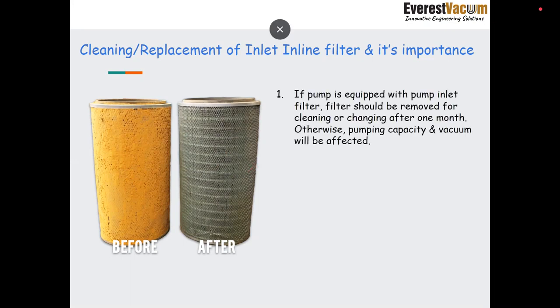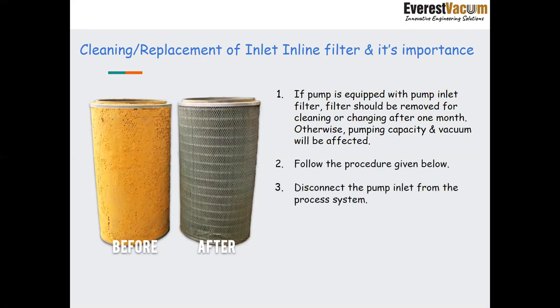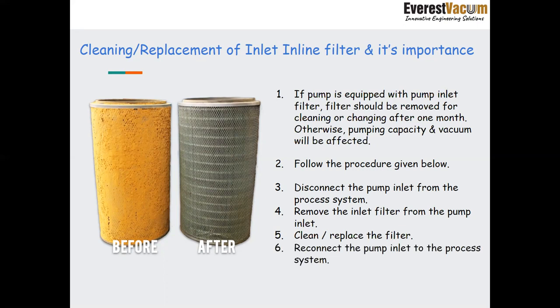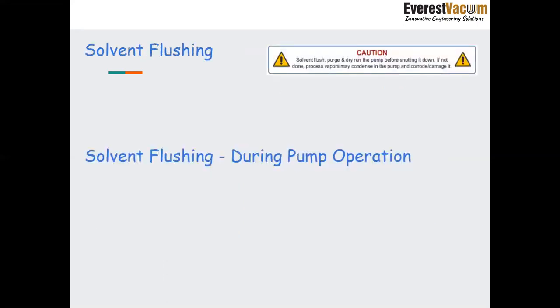So if the pump is equipped with an inlet filter, it should be removed for cleaning. Otherwise, it would lead to a drop in the pumping capacity and vacuum, which will lead to trouble in the process. So how is it to be cleaned? We need to disconnect the pump inlet from the process. We need to remove the inlet filter, and we need to clean it either with water or whatever it is miscible with, and then with clean dry air, and then we can again reconnect it to the process.